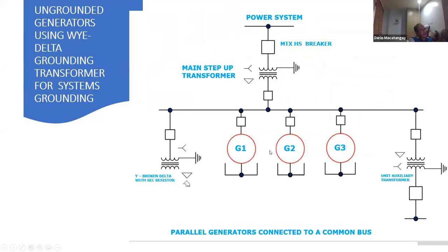Going back here, although this is a Y, it is Y ungrounded, because you can see the neutral here is ungrounded. But since this is a Y broken delta with a resistor across the broken ends of the delta winding, it's the same as a Y delta configuration. So the presence of this Y broken delta with secondary resistor is the same as using a Y delta, and it is being used as a grounding transformer here. This is how you implement neutral grounding, or earthing, in ungrounded generators.